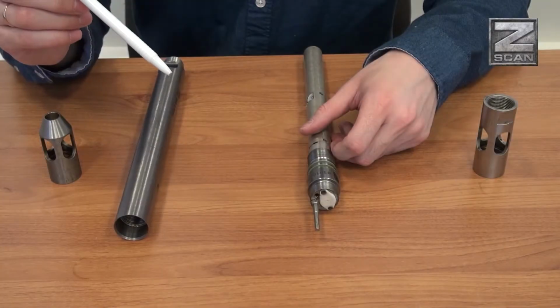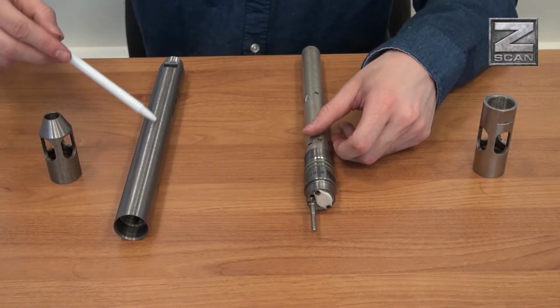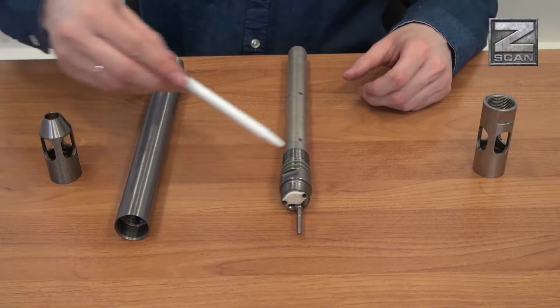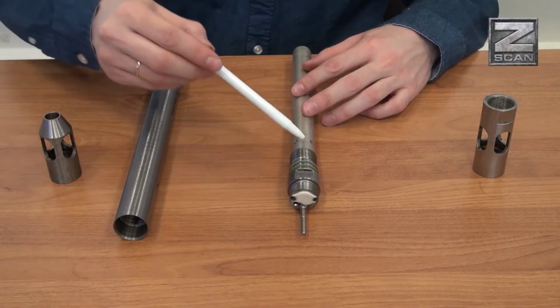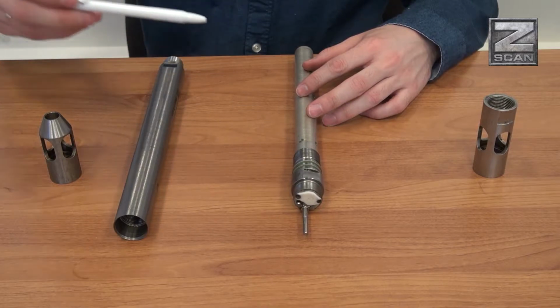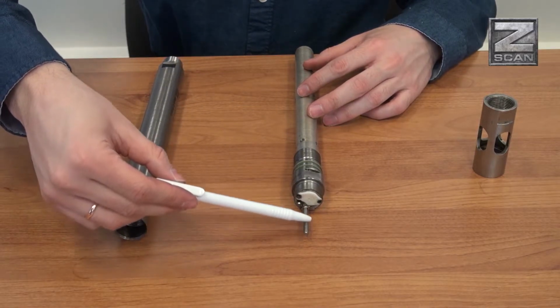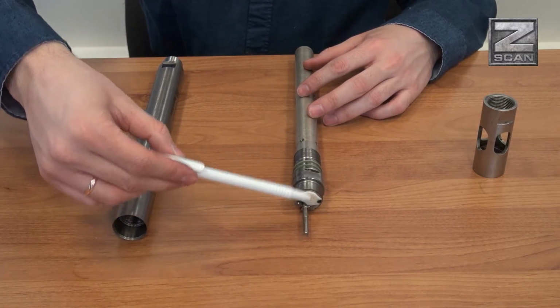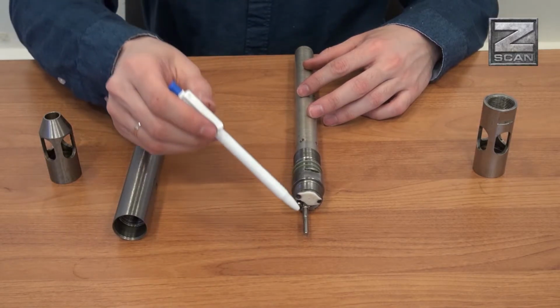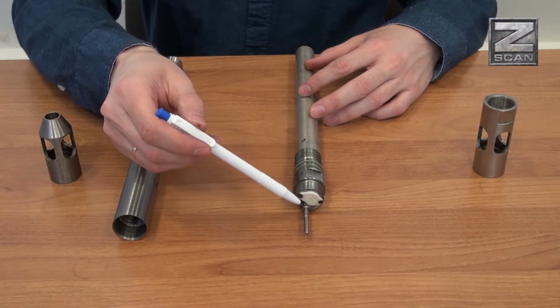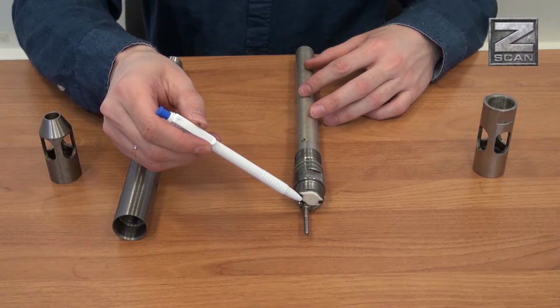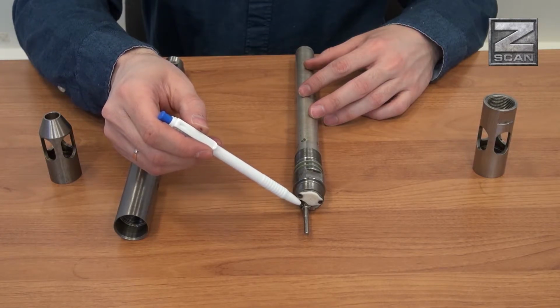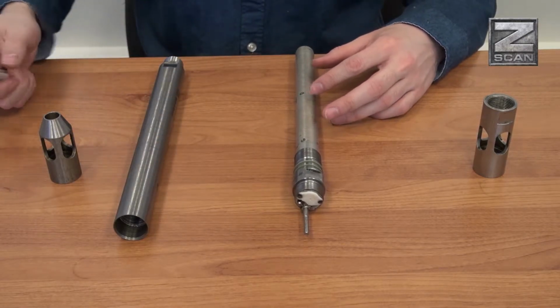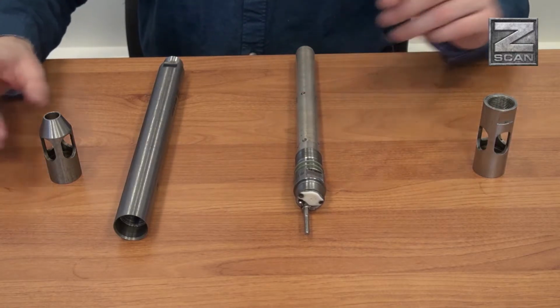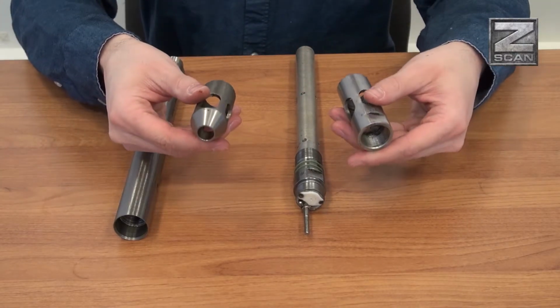The gauge has a cylindrical casing consisting of the sensor assembly and a cover connected by a thread. The measuring head has a probe and a temperature sensor at the end of the sensor assembly. The pressure sensor is also integrated into a measuring head. A special channel is made to allow free passage of fluid to the sensor. To protect the sensor, there is a bell nose with the holes for the passage of fluid.